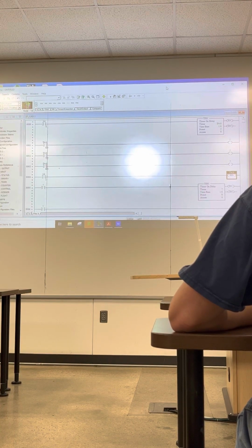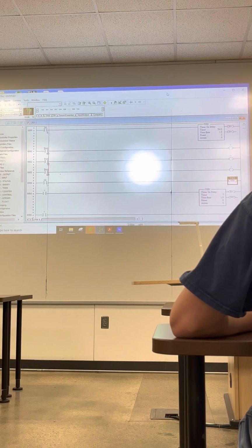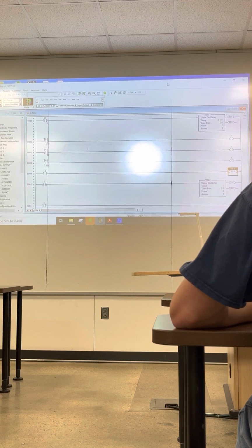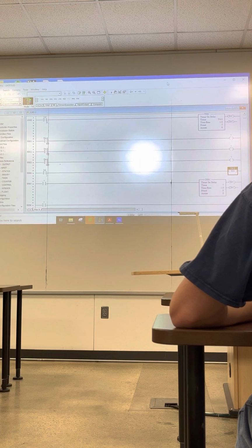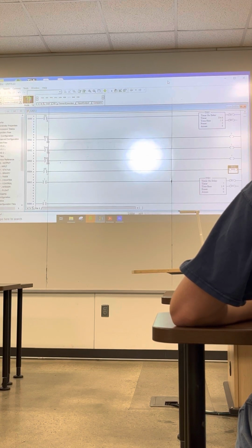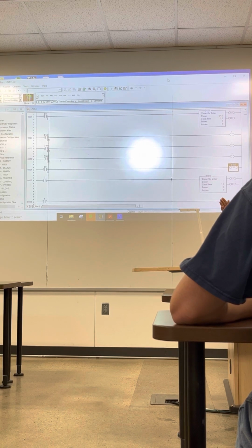Can you have a counter control another timer or a counter? Like when it's done, it makes the other counter go. You could, but when that done bit goes true, it stays true unless it's reset. So could you just have a reset? You could have a reset built in there. So this one counter counts every 12 objects, and then it goes done, and then it resets on the next one and starts counting again. As long as you get that done bit to reset each time, that other counter could tell you how many dozen objects have been made.